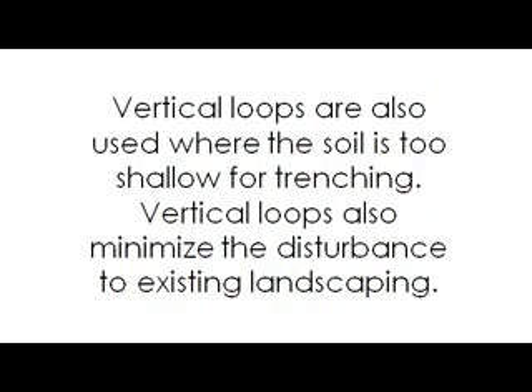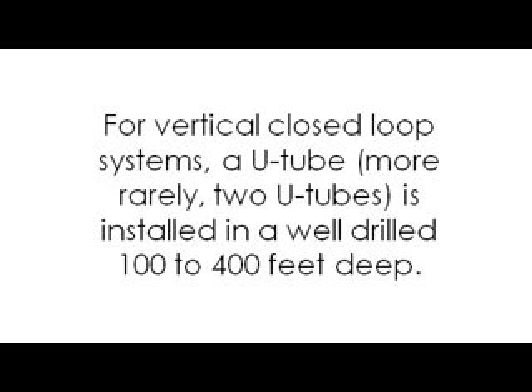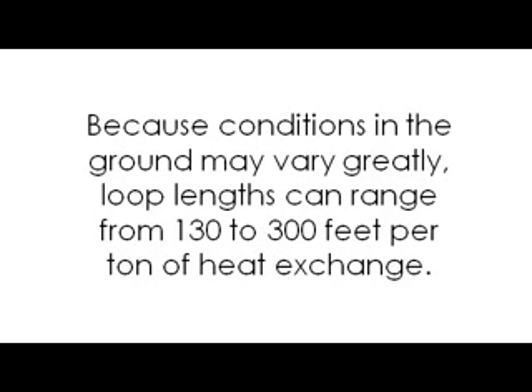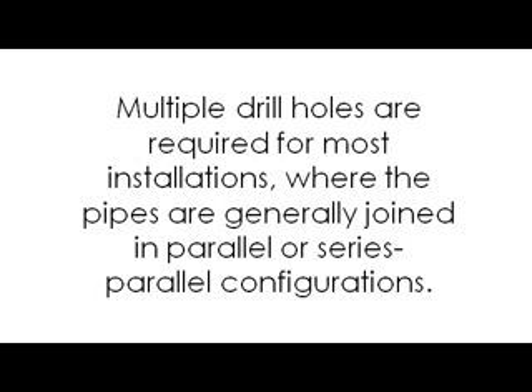Vertical loops also minimize the disturbance to existing landscaping. For vertical closed-loop systems, a U-tube, more rarely two U-tubes, is installed in a well drilled 100 to 400 feet deep. Because conditions in the ground may vary greatly, loop lengths can range from 130 to 300 feet per ton of heat exchange. Multiple drill holes are required for most installations, where the pipes are generally joined in parallel or series parallel configurations.